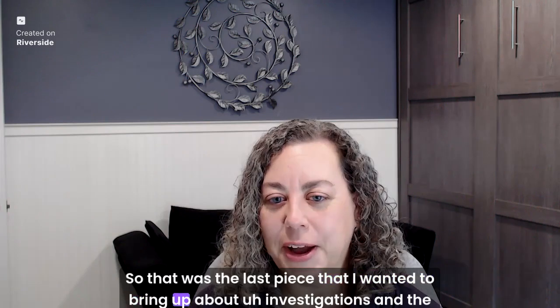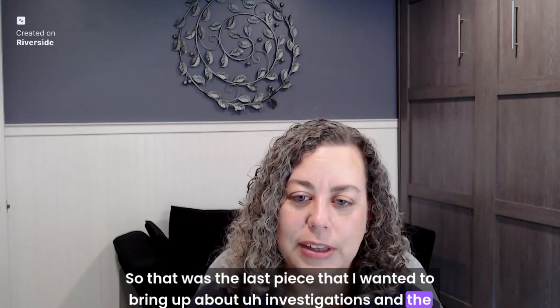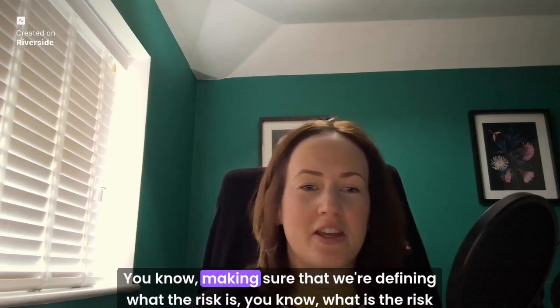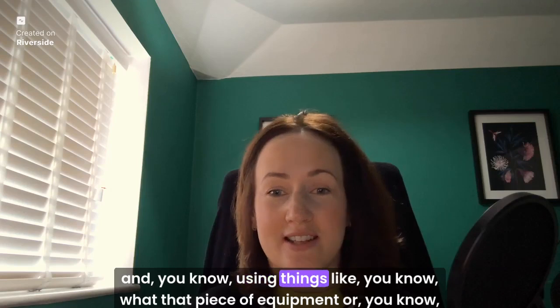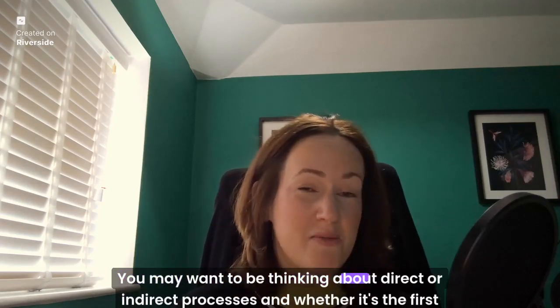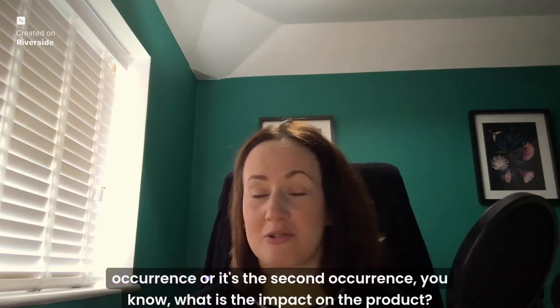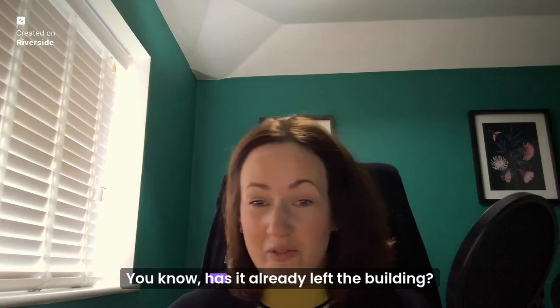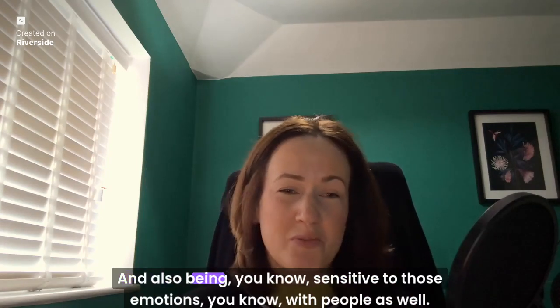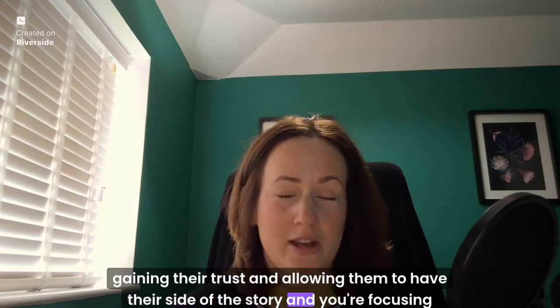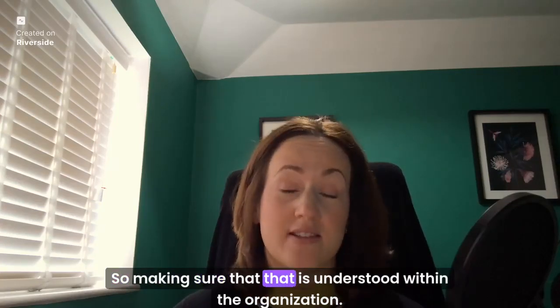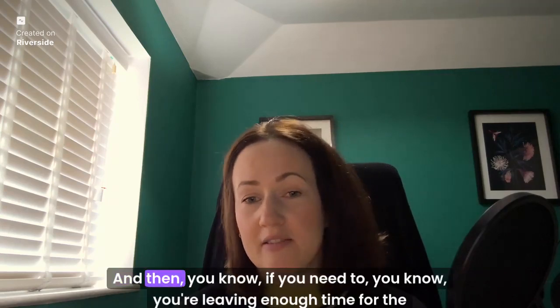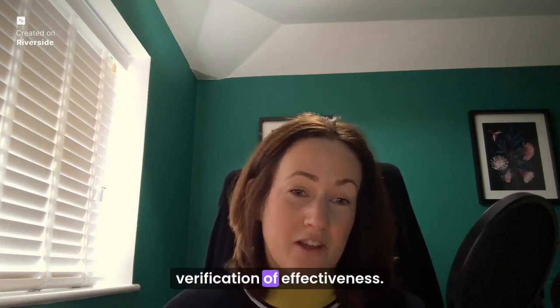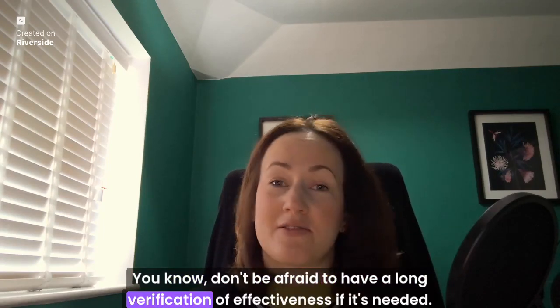So that was the last piece I wanted to bring up about investigations and the CAPAs and how we resolve those. We've covered all the good things, haven't we? Making sure that we're defining what the risk is, using things like what that piece of equipment or area is. You may want to think about direct or indirect processes, and whether it's the first or second occurrence. What is the impact on the product? Has it already left the building, or is it in house? Also being sensitive to those emotions with people, gaining their trust and allowing them to have their side of the story, while focusing on the process, not the person. Making sure that is understood within the organisation. And then, if you need to, leaving enough time for the verification of effectiveness. Don't be afraid to have a long verification of effectiveness if it's needed.